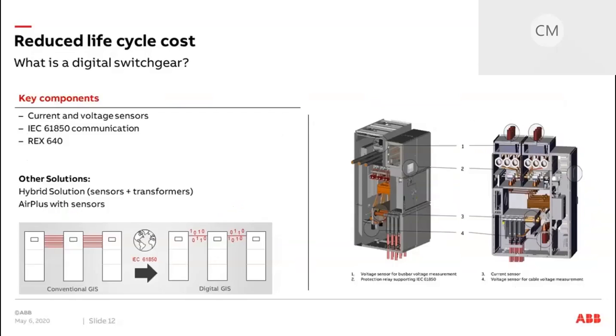So having a closer look on digital switchgear, we usually use outer cone feeders, as you can see on the right side, and so these sensors for current measurements will be located on the outer cones of the panels. If you would like to have revenue metering, you can combine for this particular feeder a sensor for protection and a conventional current transformer for revenue metering, because the sensor accuracy is maximum 0.5. If you require 0.2, you would add a conventional transformer.